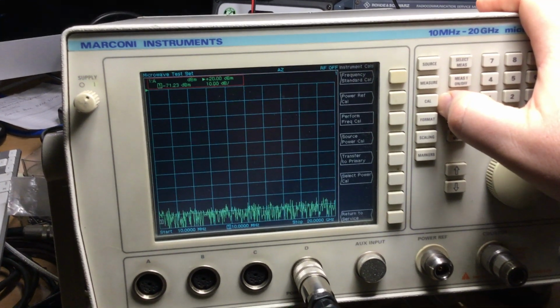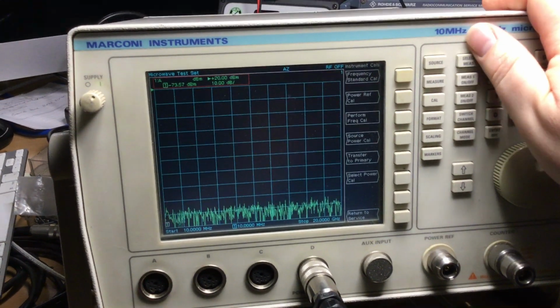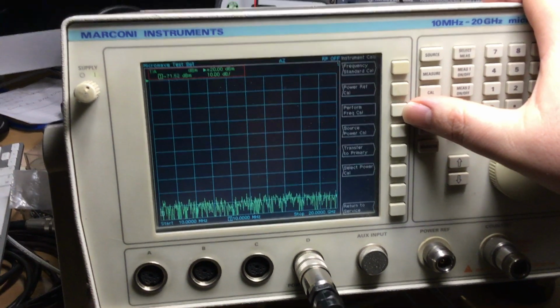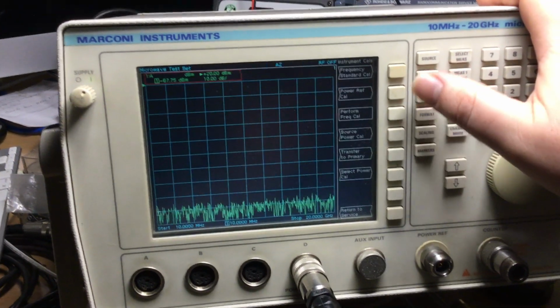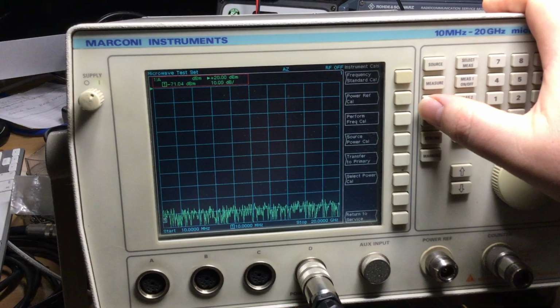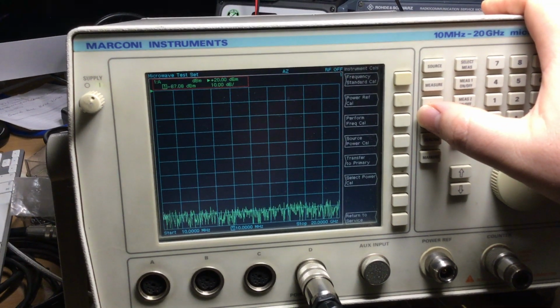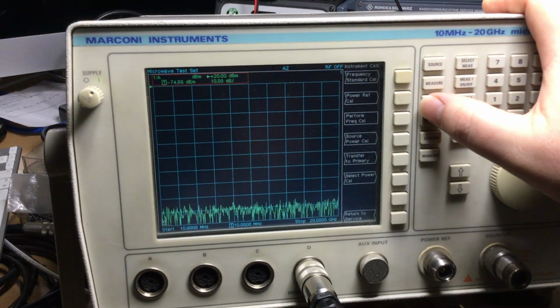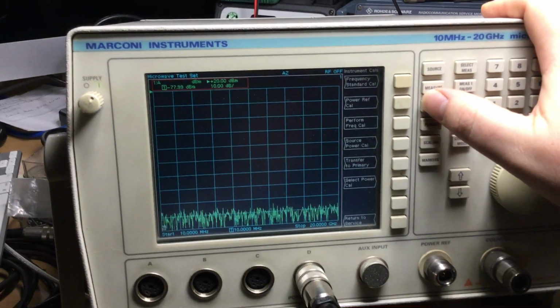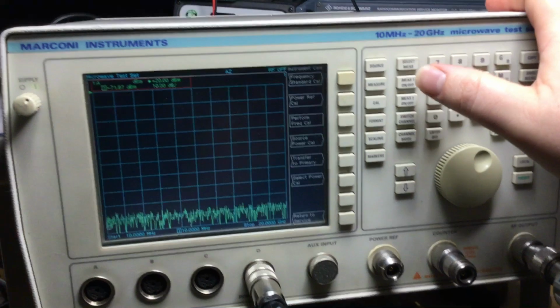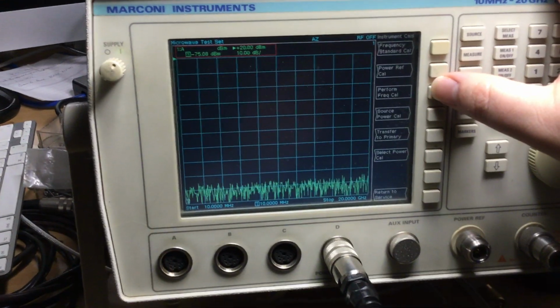If you look in the service manual for this test set, it gives you the information of how to transpose a serial number. There's a conversion part to it where you convert the serial number into other alphanumeric characters, and that then gives you the password that you have to enter to get into the calibrations menu.